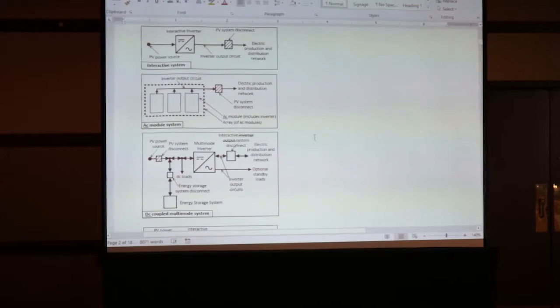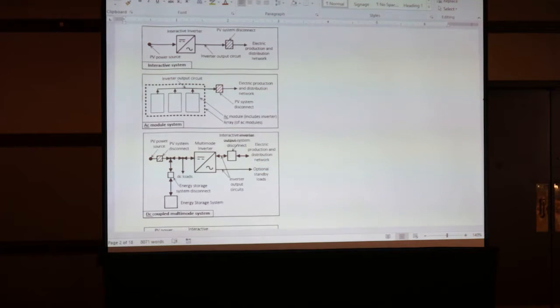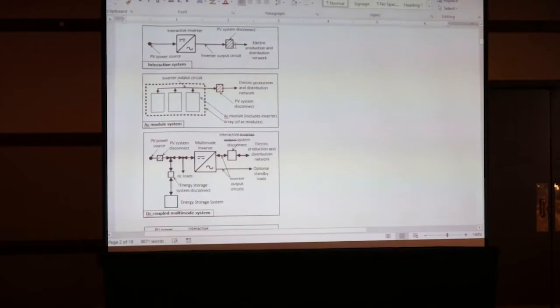Okay, so let's talk about what the code says right now. The 2017 code defines this thing called a PV system disconnecting means. In this case, a PV system disconnect would be the noun. So the way to think about what a PV system disconnect is, if we're standing at the PV system disconnect and we look toward the solar panels, I'll use panels instead of modules, but we all know they're modules, but everybody else in the world calls them panels.